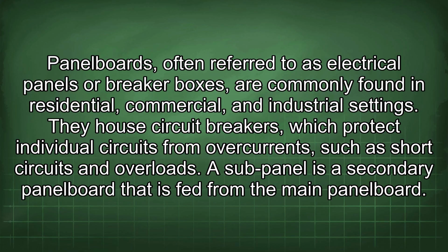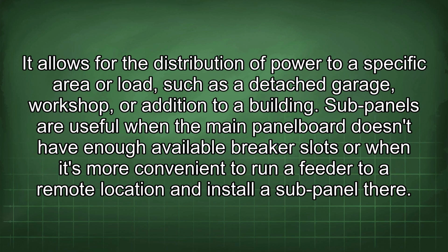A subpanel is a secondary panel board that is fed from the main panel board. It allows for the distribution of power to a specific area or load, such as a detached garage, workshop, or addition to a building. Subpanels are useful when the main panel board doesn't have enough available breaker slots or when it's more convenient to run a feeder to a remote location and install a subpanel there.